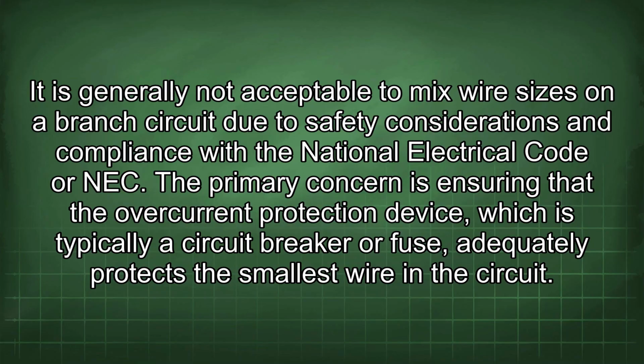It is generally not acceptable to mix wire sizes on a branch circuit due to safety considerations and compliance with the National Electrical Code, or NEC. The primary concern is ensuring that the overcurrent protection device, which is typically a circuit breaker or fuse, adequately protects the smallest wire in the circuit.